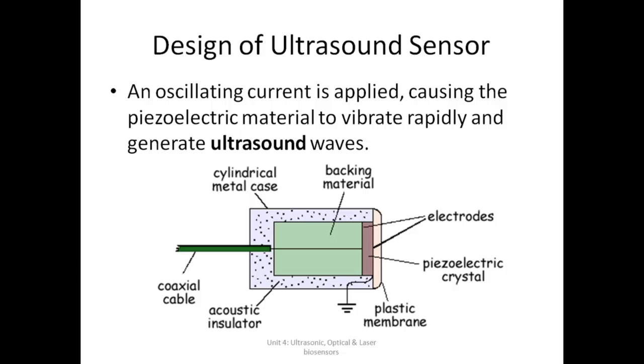This whole housing is inside a metal case, and you can see that at the outer boundary you have an acoustic insulator. The acoustic insulator is required so that the signal doesn't get lost, and there is no acoustic disturbance coming into the picture. So both ways, the original signal should not get lost, and any unwanted acoustic signal should not enter into the probe. And at the back you can see there's a coaxial cable. This is connected to your machine. So this is what an ultrasound sensor or an ultrasound probe actually looks like.